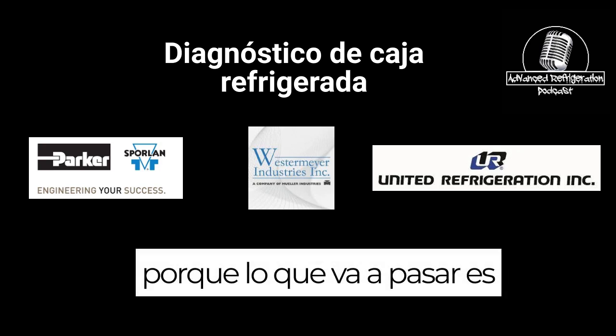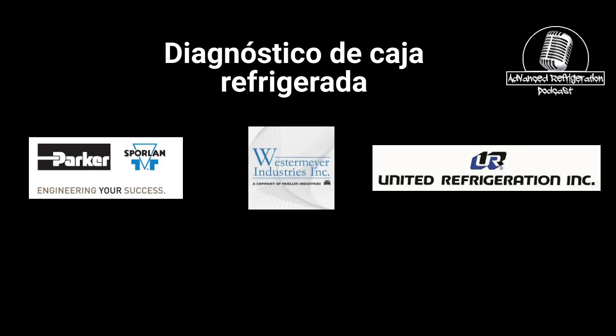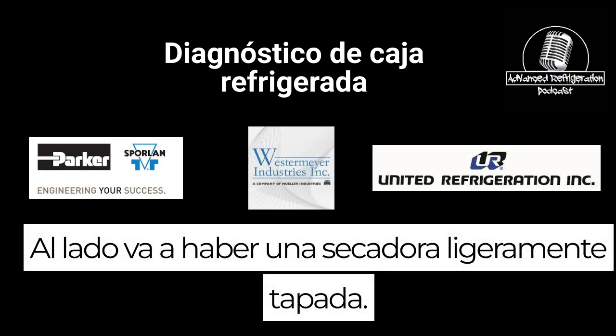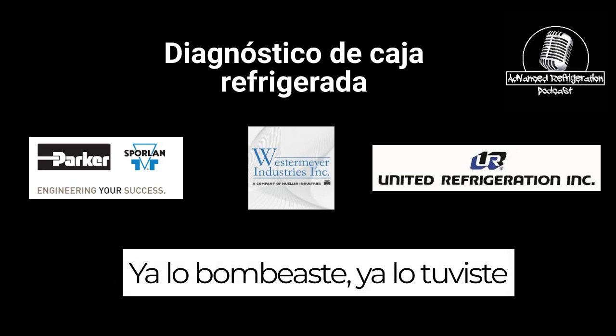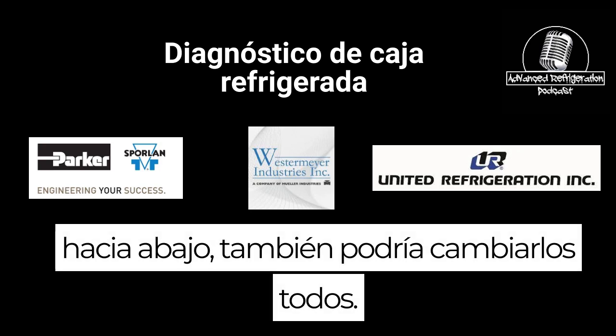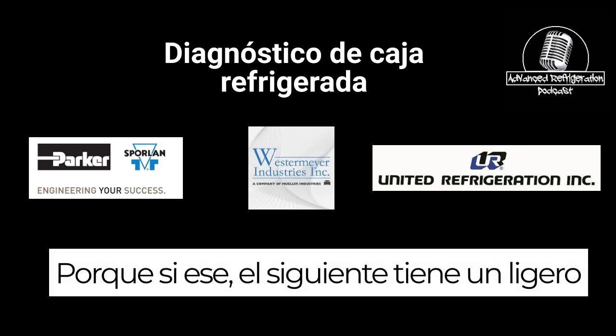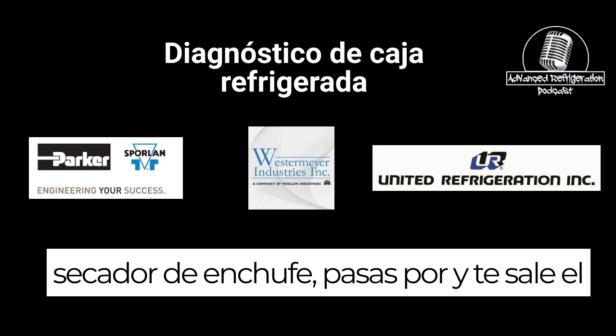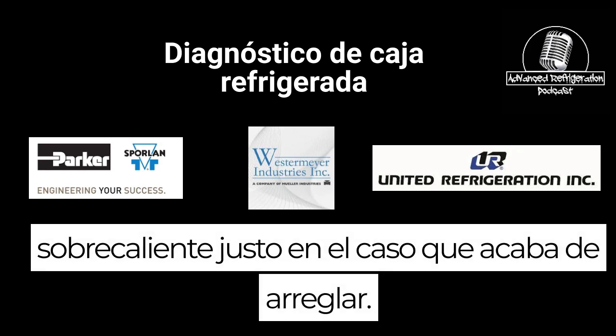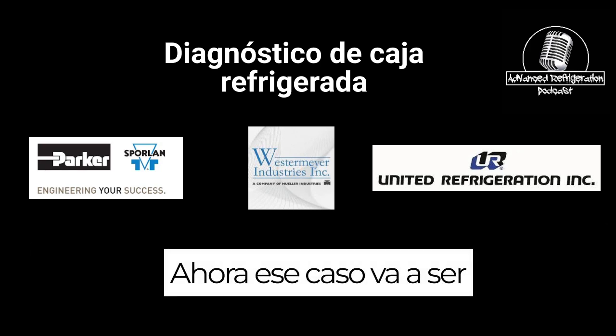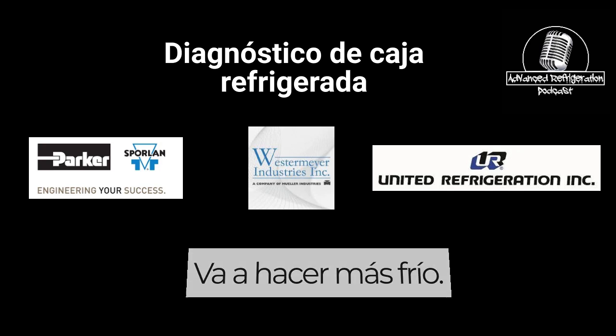Because what's going to happen is that case next to it is going to have a slightly plugged dryer. You already pumped it down. You already had it down. You might as well change them all, because if that one next to it has a slightly plugged dryer, you go through and get the superheat right on the case you just fixed. Now that case is going to be out of balance with the other case. It's going to be running colder.